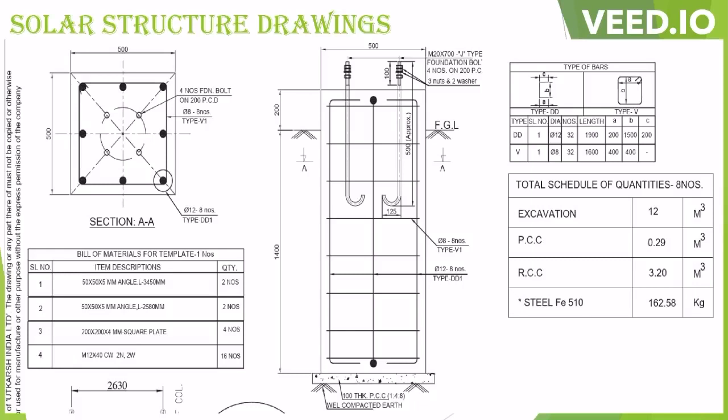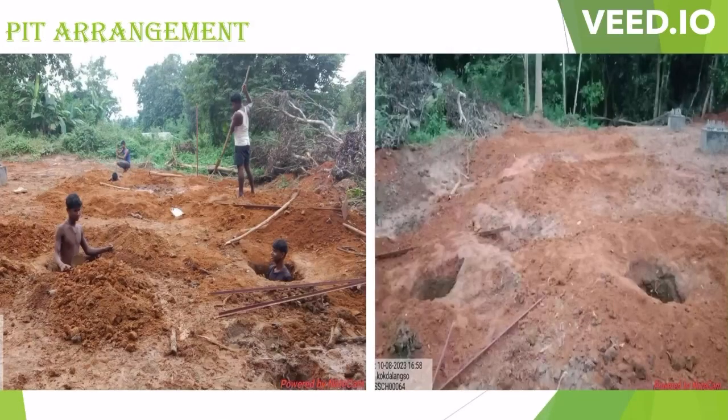As mentioned earlier, this work must be started only after getting the foundation bolt and template. From the drawing you can also see the rod size and cutting length required for the structure work, and the top view of the arrangement of foundation bolts to be put into the pit. There are 4 foundation bolts required per pit. The pit digging must be a minimum of 1.5 meters depth, and for one 5 kilowatt plus 5 kilowatt unit, we need to make 8 numbers of pit arrangements.